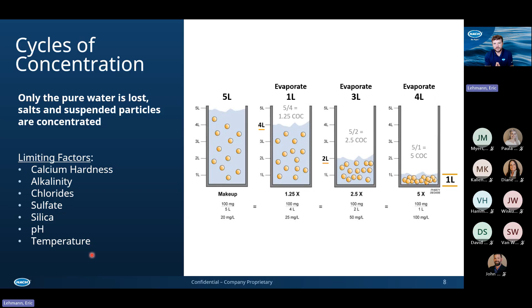So when they're operating a cooling tower, they're limited by the number of cycles they can run on it before they have to perform a blowdown or get rid of that cycled up water, the concentrated water. So there are some limiting factors when it comes to those impurities. Oftentimes we're looking at calcium hardness, alkalinity, chlorides, sulfate, silica, pH, and temperature. So those are some common parameters they look at for the cycles of concentration. But in a few more slides, we're going to talk about some other parameters they might be monitoring.